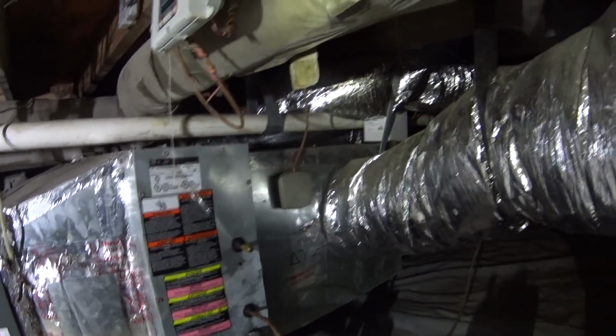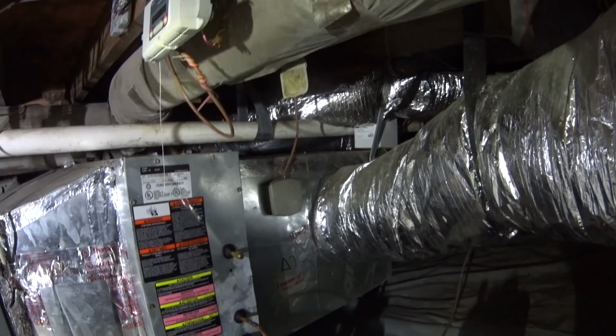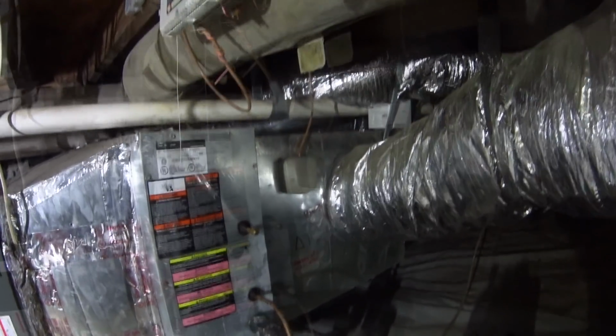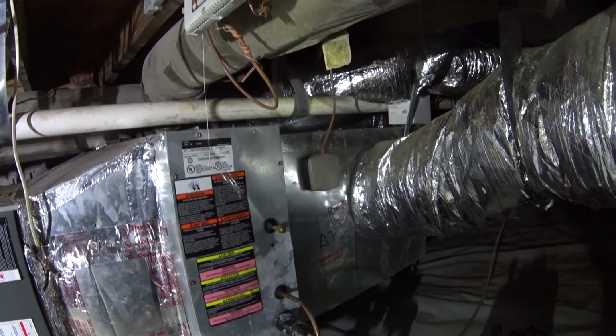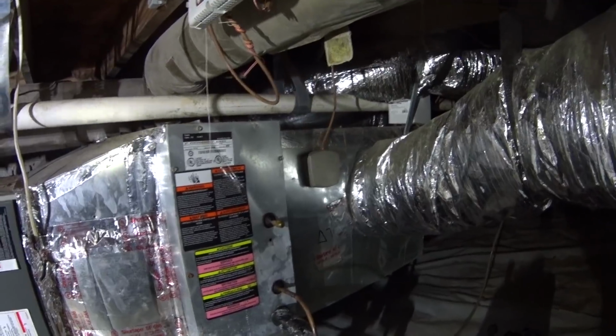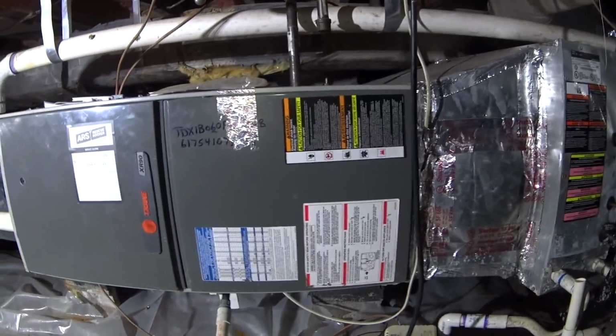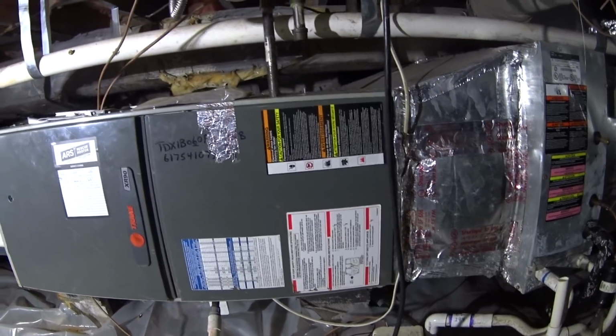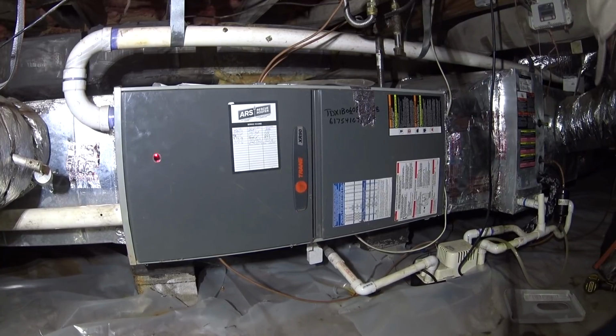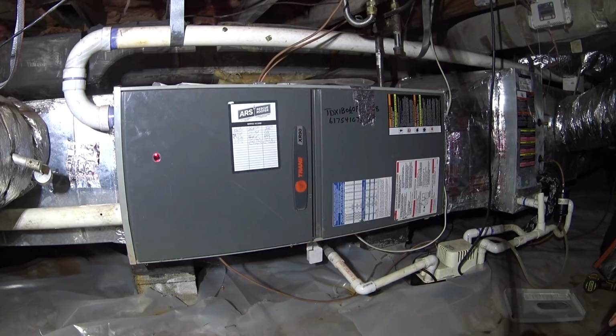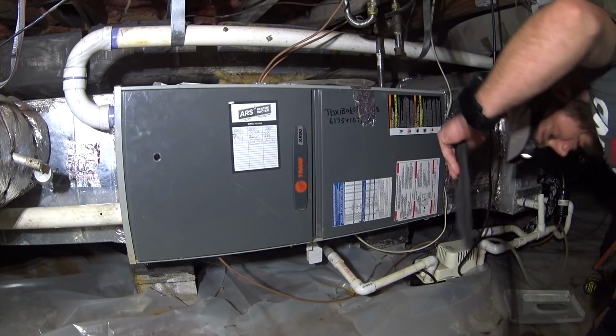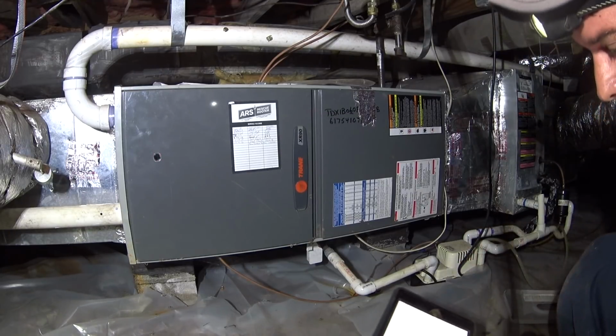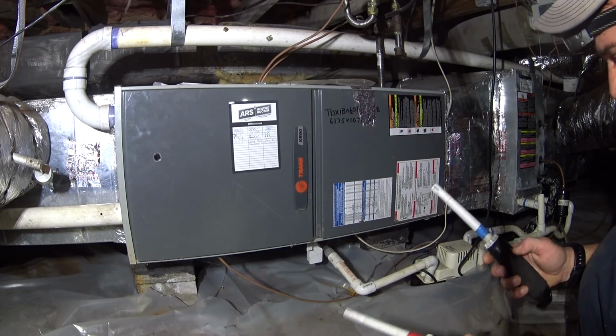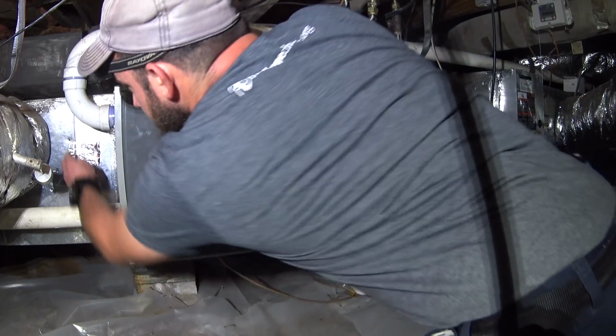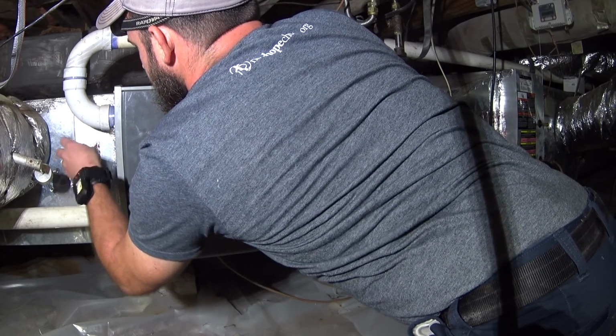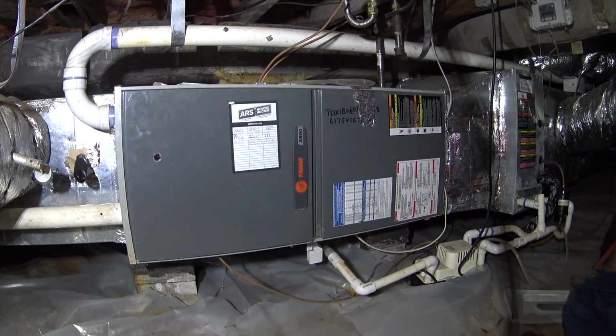And since my plenum is all of 30 inches or so, I don't have a whole lot of space to put that somewhere else. But ultimately I like to have it down farther on the supply plenum. So I'm gonna get the camera in a static position and we'll dig into this sucker. I think that perspective will work for the time being. I'm going to go ahead and fire up the iConnect and place my air probes for that. Return sensor and supply sensor goes over here.